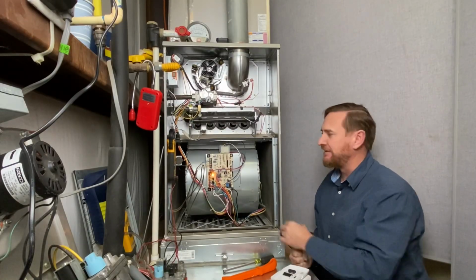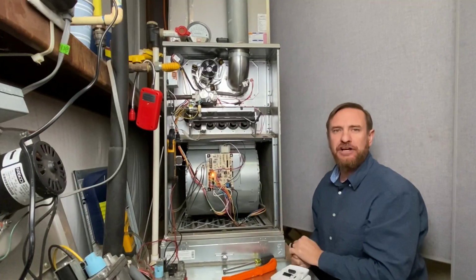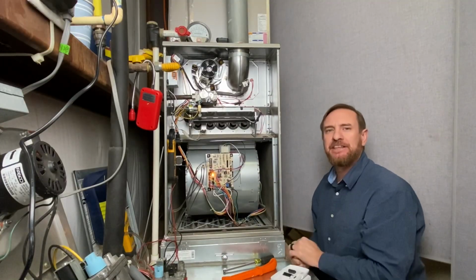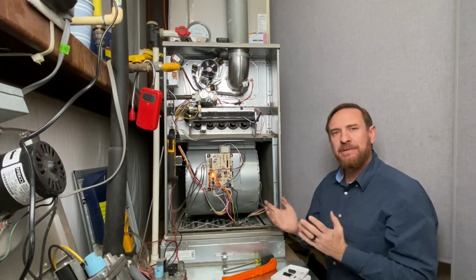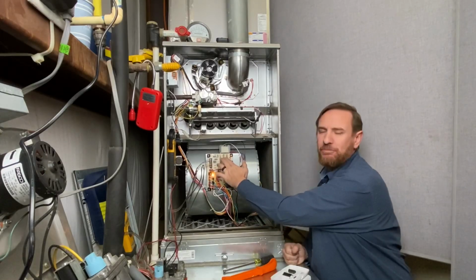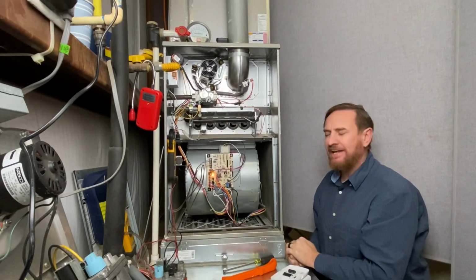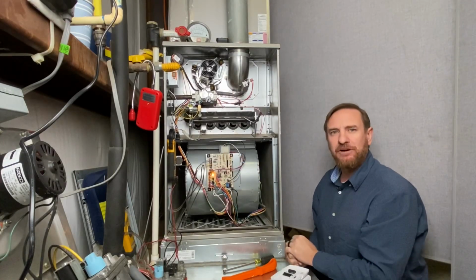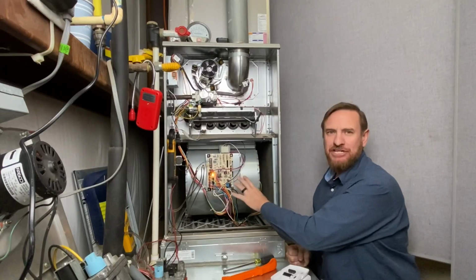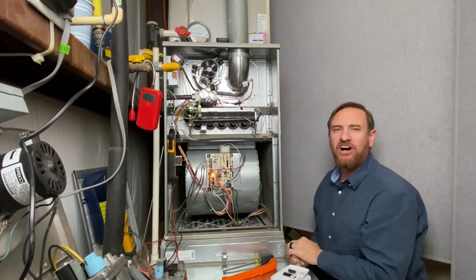For efficiency, you want the blower to run for as long as possible, so you get every little bit of that heat into the house. So it's always a balance. Most control boards allow you to adjust that off delay, but I have yet to see a control board anytime recently that had the ability to adjust the on delay.